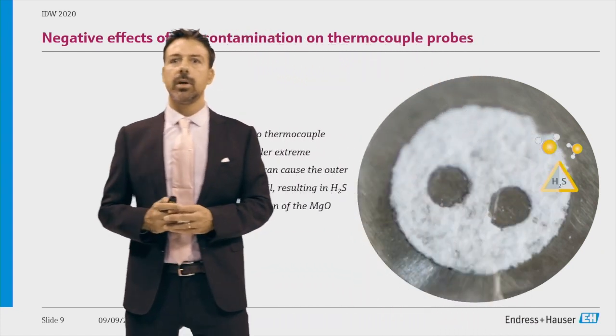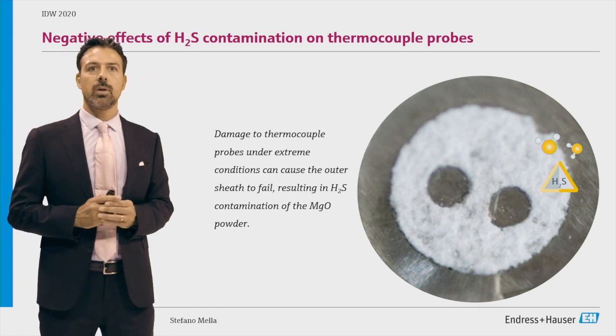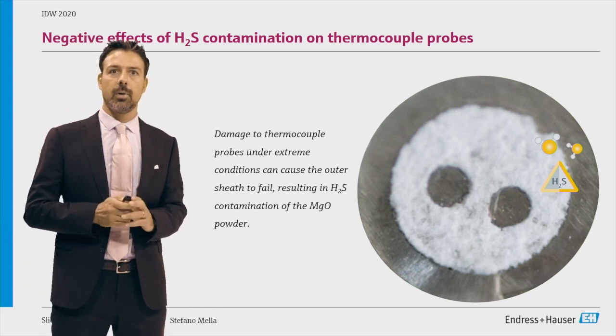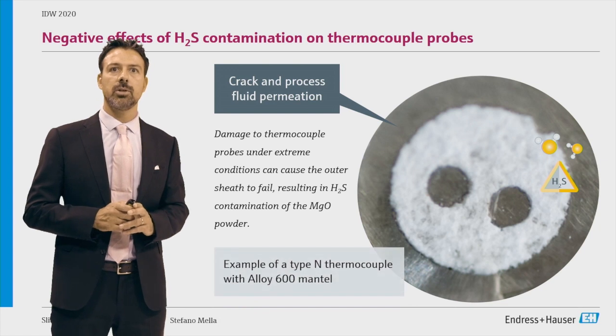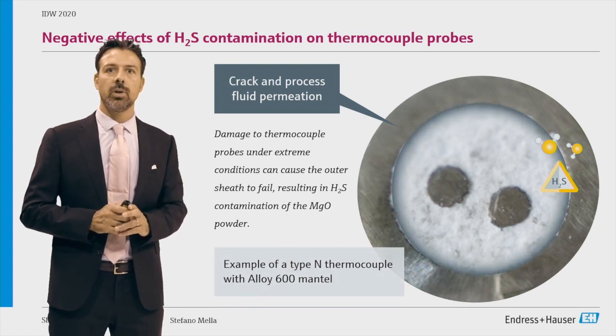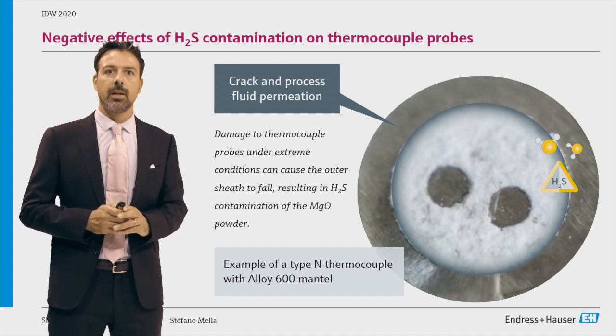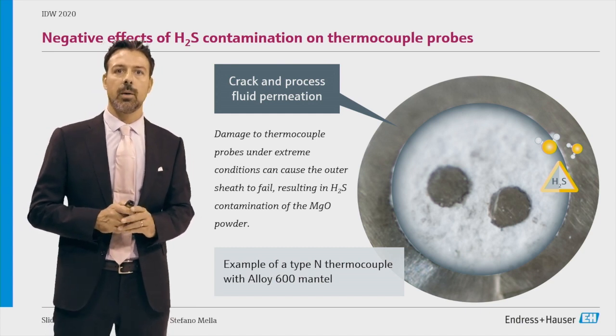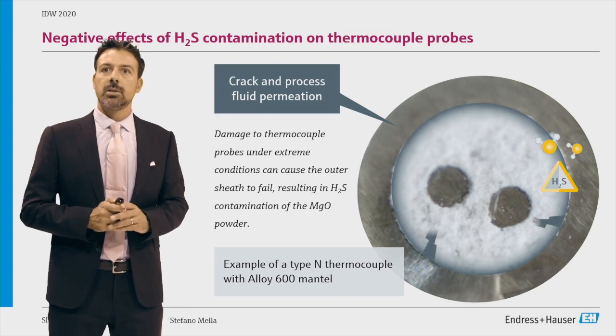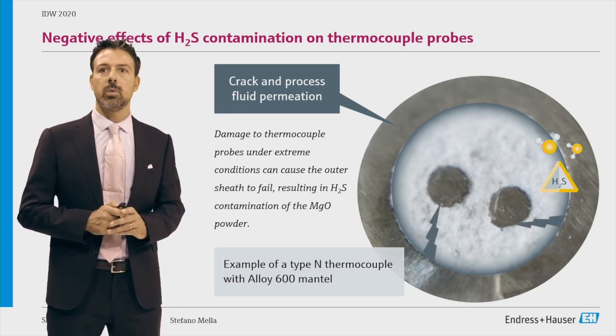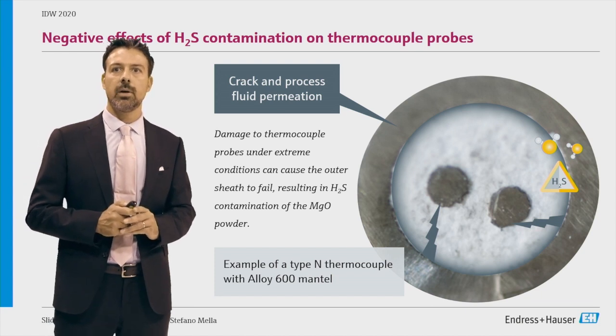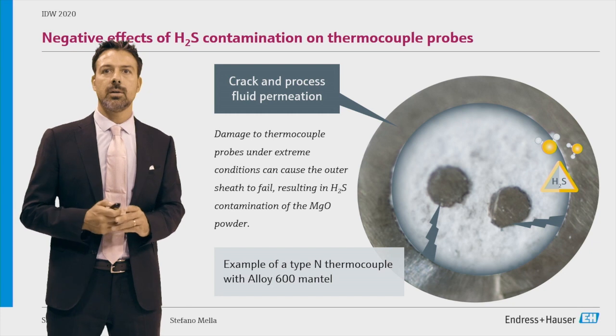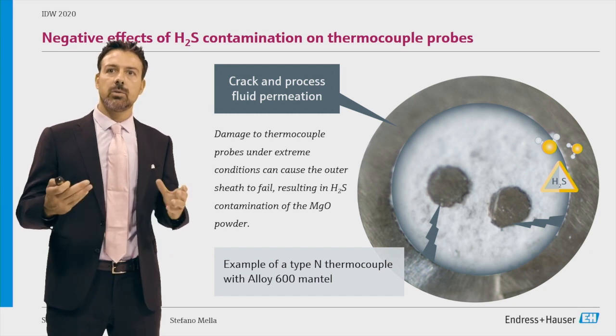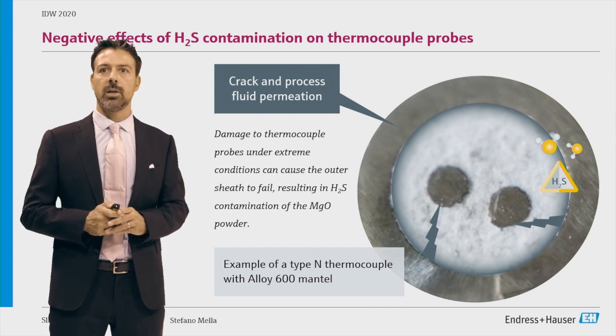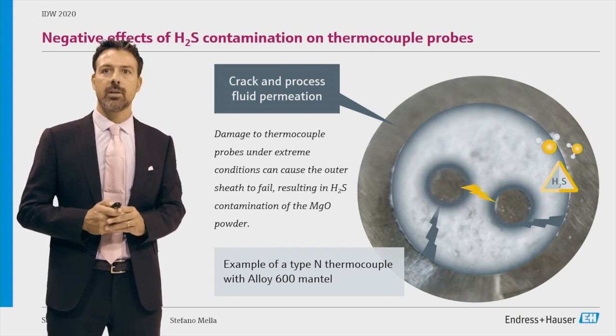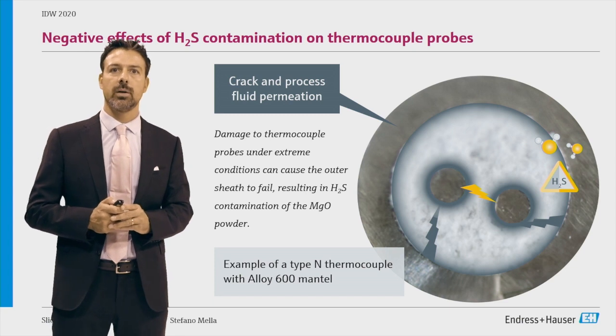Here I want to explain in more detail and with an easy animation what is happening on a typical thermocouple. So let's assume we have damage on the outer sheath, so a crack, and the process fluid goes into the thermocouple. In this specific example, we have a type N thermocouple with an alloy 600 mantle. So the fluid will start quite quickly to diffuse into the mineral insulated powder, from the inner wires outside to the rest of the powder. And the negative effect is a short circuit between the two wires.